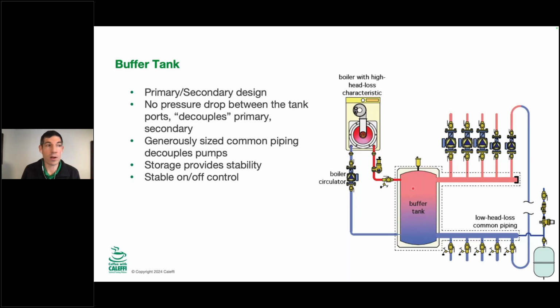It absolutely will work as primary secondary piping because it's just a really oversized hydro separator. So if you had 10 GPM here, it's going to go into the boiler. If you have 100 GPM on this side, this vessel is big enough that it can just kind of spin around really fast without fighting with the other side of the equation in our primary secondary piping diagram here.